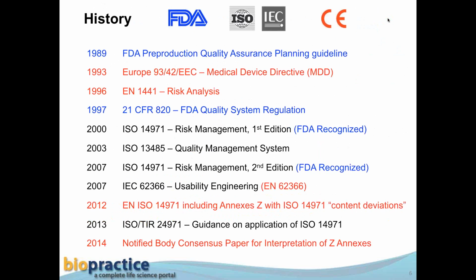But FDA has recognized ISO 14971. There's a first edition and then a second edition in 2007. And that's kind of where it stops with FDA as far as 14971. In Europe, there's been more expanded interpretations of risk management and what it must entail. And that's really related to the directives in Europe.